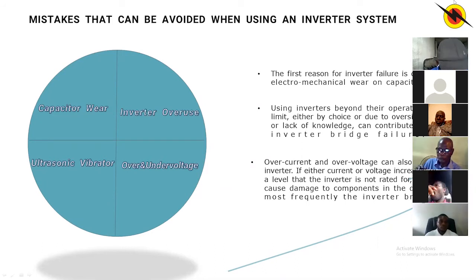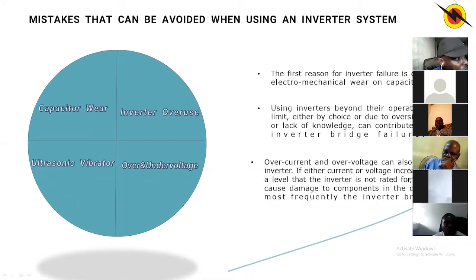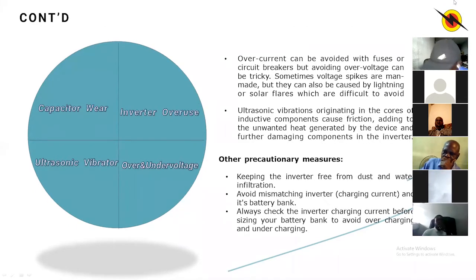You really need to check because it depends on the battery type and the age of the battery. If the battery is aged, like let's say you've been using it for over a year, and it's a lead acid battery, just forget about trying to put additional batteries to that battery bank, because what will happen is that the new batteries are going to absorb the characteristics of the old, weak batteries, and so you're also not going to get good value for your money. So that's what we don't want to do. For the lithium ion batteries, you can always stack them. It doesn't matter if you've been using them for 1 year, 2 years, because they have internal circuitry that controls the charging parameters of the battery. So it enables the lithium ion batteries to always charge independently.